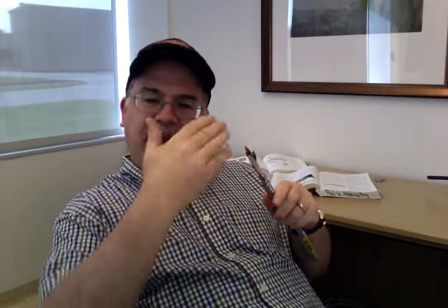Now, what also makes it different is the termination aspect of it. What do you do with this 10 gauge? You don't take it into the fitting, you don't take it into the box. You simply take this, you bend it back, you cut it away just on the inside so it doesn't protrude past the outer perimeter of the armor, and that's it. It's done. Now the fitting will fit over the conductors and onto the armor without this aluminum conductor getting in the way. So we don't want this to inhibit the actual connector from fitting onto the armor.